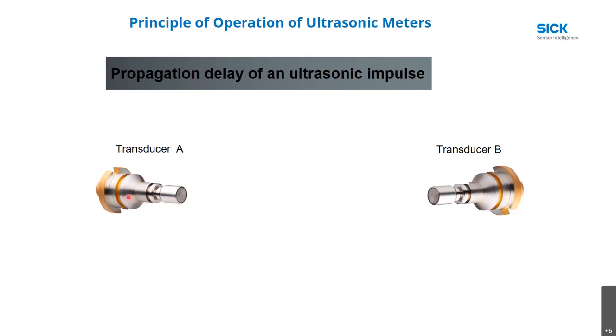These transducers are made of titanium. They're very durable, and they're encapsulated, so nothing can get inside the transducer to damage them. The mean time between failures is approximately 15 years, so they're very durable. About the only thing you would ever have to do is, if something came down the pipeline and accumulated on the face of the transducer, you could blow the line down, pull them out, and clean them, depending on which model you have.